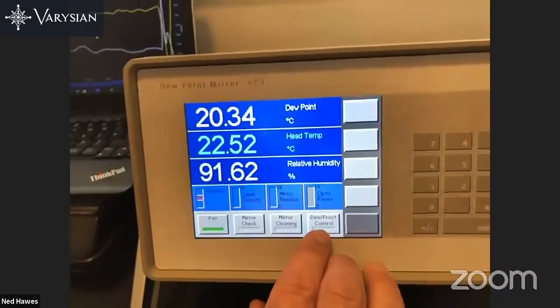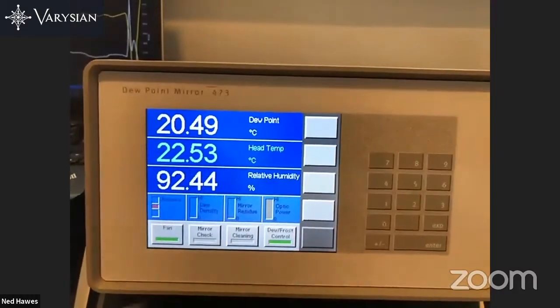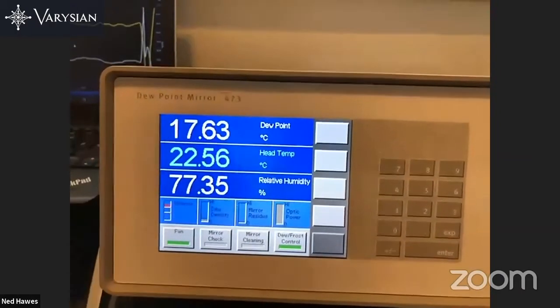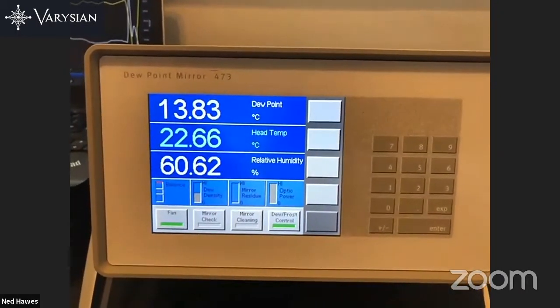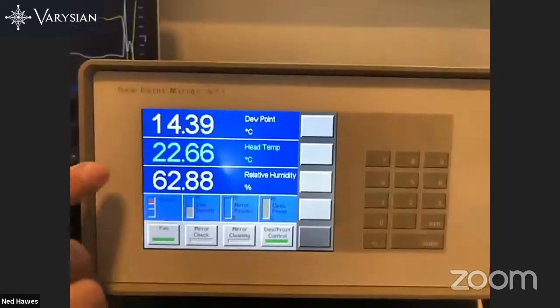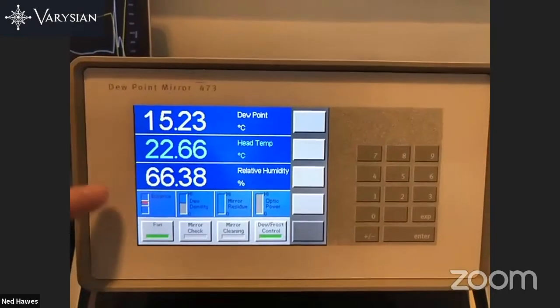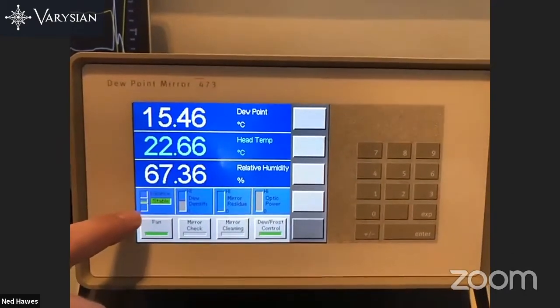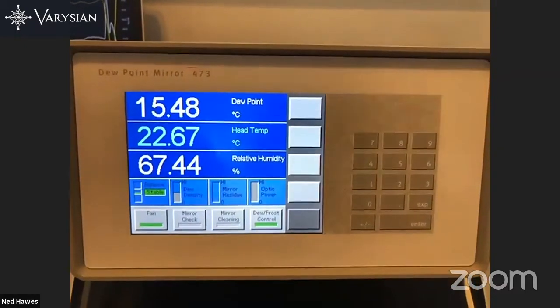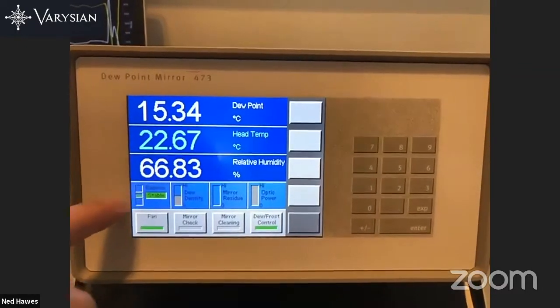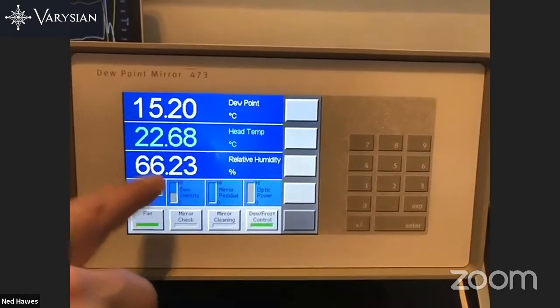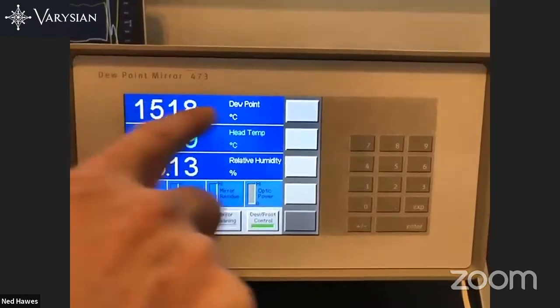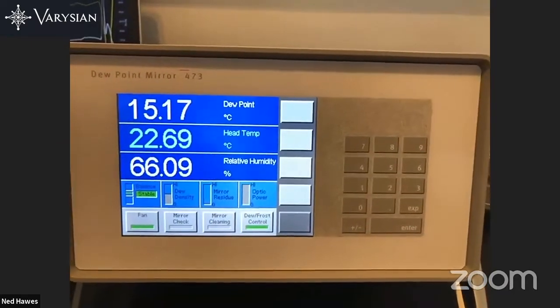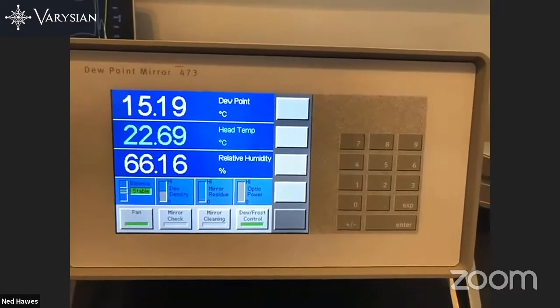Notice that when I press dew frost control on this, it controls the temperature of the mirror to the point at which the dew or frost film forms. I'll turn that on now, and that will take the temperature down. It comes to a point where it becomes a stable layer on the mirror surface, and at that point we have a real value. That's a stable dew or frost film on the mirror, because the temperature is being controlled to the dew point of the condition.